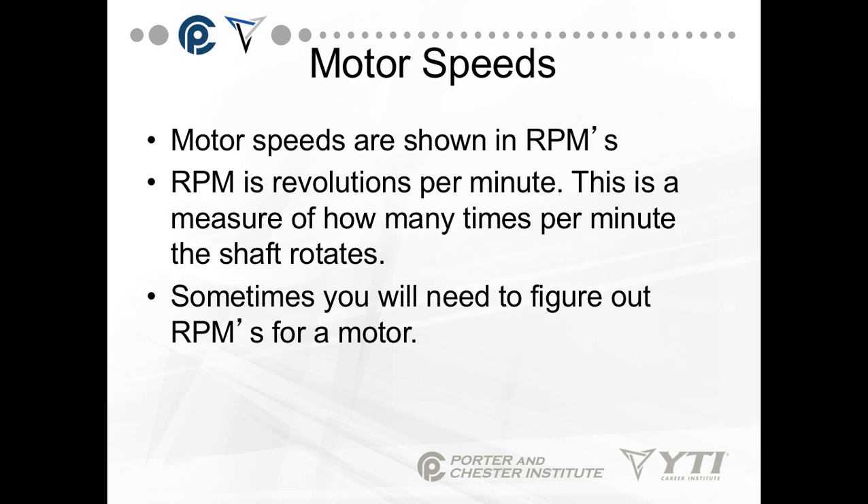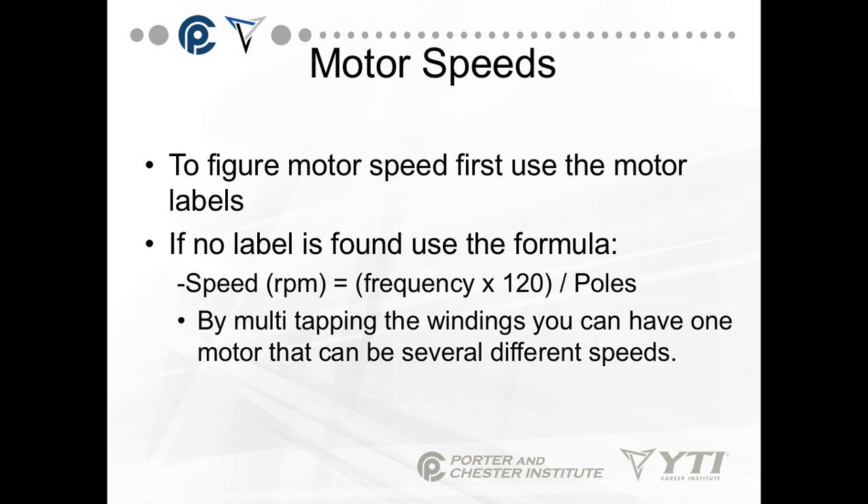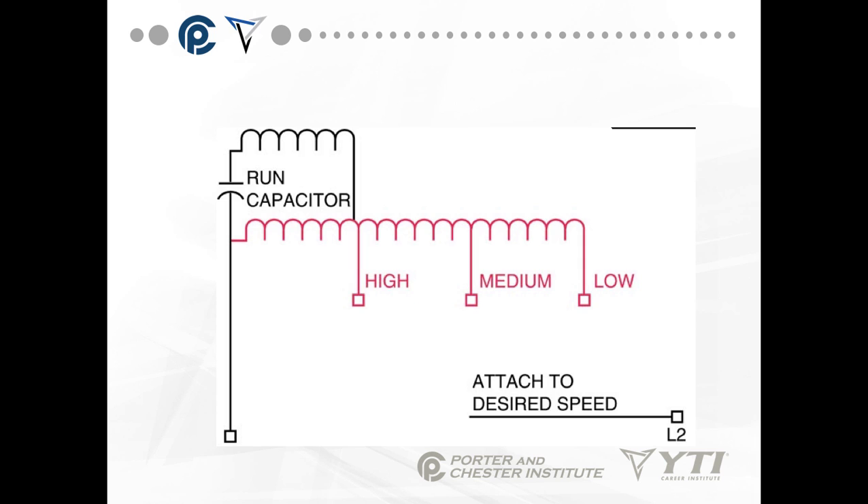Motor speeds are shown in RPMs — revolutions per minute — a measurement of how many times per minute the shaft rotates. If the nameplate is missing or unreadable, you can calculate motor speed using this formula: RPM equals frequency times 120, divided by the number of poles. In the United States, frequency is 60 hertz. By multi-tapping the windings, you can have one motor with several different speeds.